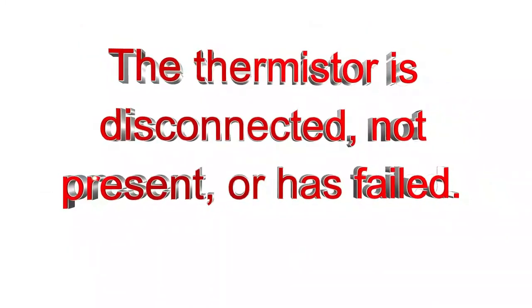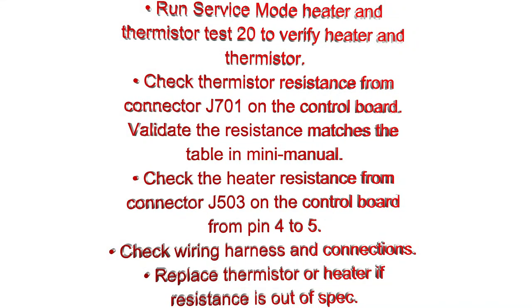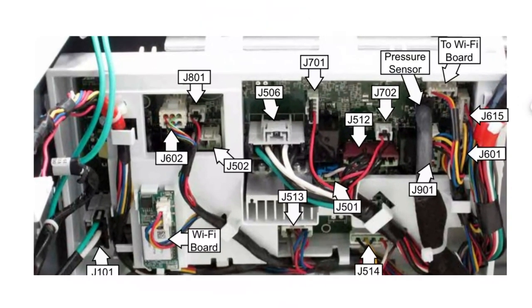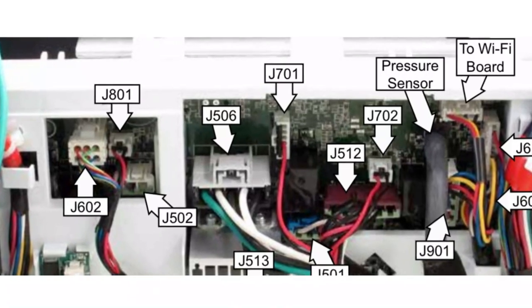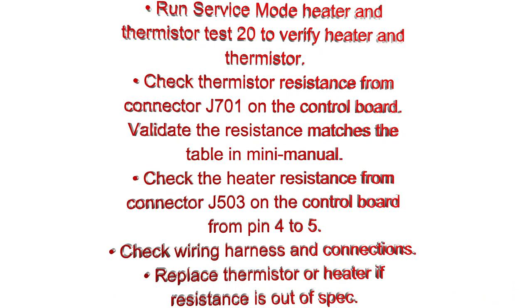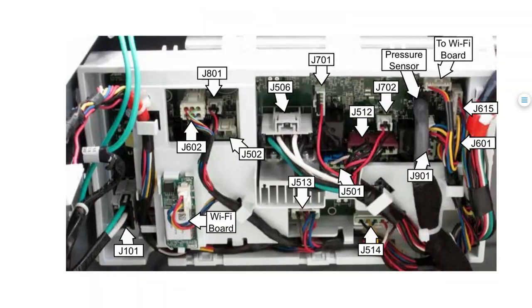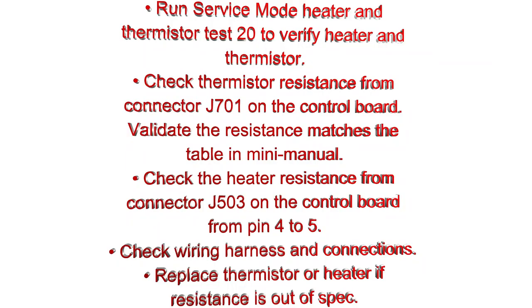Error 15, water temp sensor invalid. The thermistor is disconnected, not present, or has failed. Run service mode heater and thermistor test 20 to verify the heater and thermistor. Check thermistor resistance from connector J701 on the control board. Validate the resistance matches the table in the mini manual. Check the heater resistance from connector J503 on the control board from pin 4 to 5. Check wiring harness and connections. Replace the thermistor or heater if resistance is out of spec.